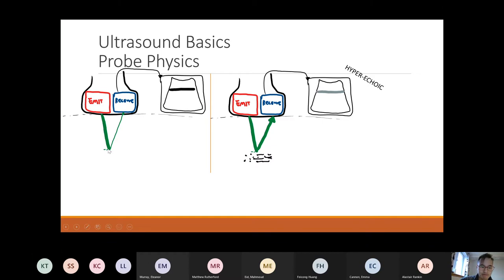Your probe emits ultrasound, and at every level a small portion of that ultrasound is reflected back. This is just one level I've drawn, but it happens at every level. A small portion, represented by the thin line here, is reflected back, and the receiver detects the wave that's reflected back, as well as the intensity or amount of ultrasound reflected back from that level. Depending on the intensity it detects, it assigns a shade of gray on your screen and projects it.